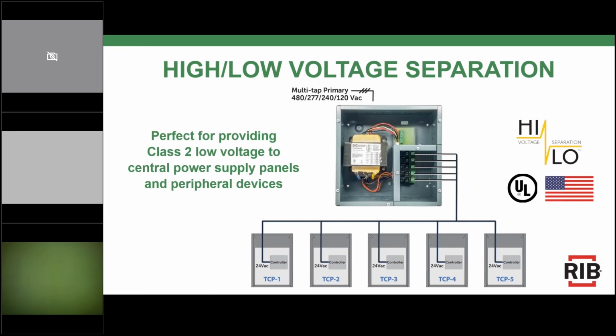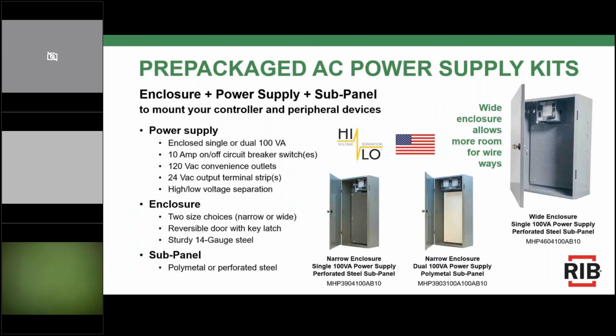So here's a nice picture of that. It kind of shows you the design of the power supply. It is a multi-tap primary. You've got those class 2 low voltage outputs. As you can see here in this example, this is just showing you how you can send those off into your temperature control panels in maybe 5 different zones or 5 different building areas.